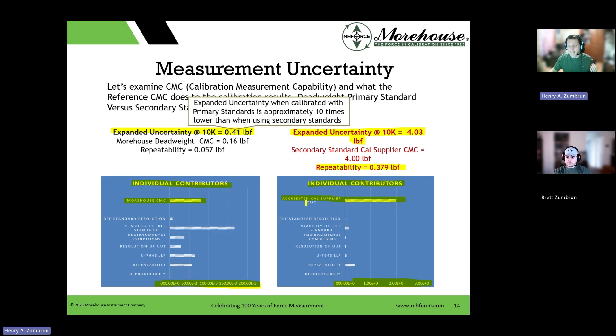So if you ignore the numbers, the whole piece of this expanded uncertainty when calibrated with primary standards is 0.41 pounds force, and then calibrated with that benchtop machine, that same load cell, when we do the traceability aspect and do uncertainty for it, is 4.03. So this is almost a 10x multiple overall. But it is important to look at those graphs and everything, because the side on the left is really good analysis.